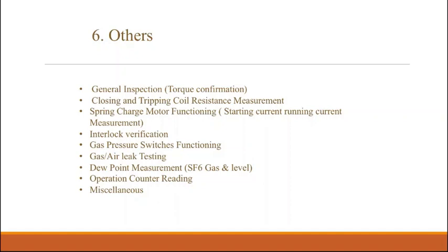And here there is the operation counter reading. Each time we operate the breaker, one tripping and one closing, there is a counter available. The integrator counter will start adding. The manufacturer will give a warranty such that this particular breaker can be used for 10,000 operations, 50,000 operations, or 1 lakh operations. For that purpose, the operation counter reading is most important.